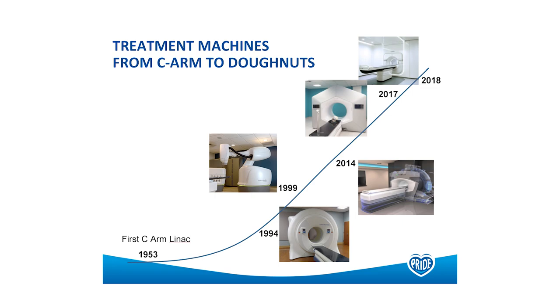Rock Mackie introduced the TomoTherapy Unit in 1994, quite revolutionary at the time. By 2014 we had the first ViewRay MR-guided system — MR-cobalt at that point — and by 2017 we had an MR-Linac version, and Elekta weren't far behind. Their MR-Linac was in research mode for quite a long time, but gained CE marking in 2018. At the same time, the Halcyon was released in 2017 — a completely different take for Varian, moving away from the C-arm platform.